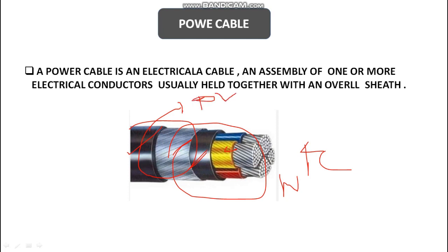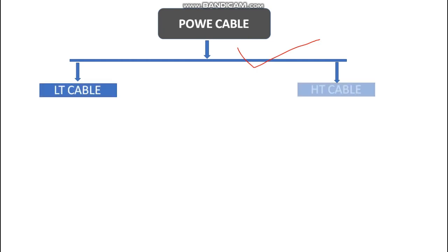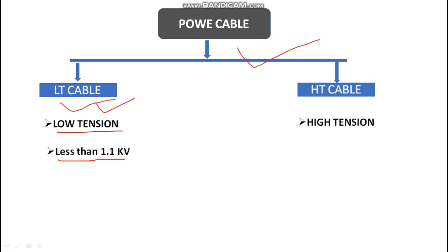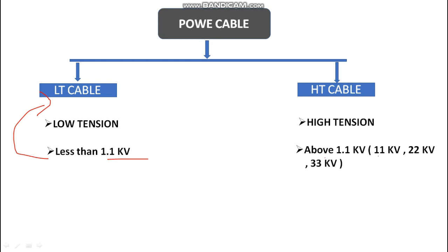Power cable also has types: LT cable and HT cable. LT cable means low tension cable, and HT cable means high tension cable. LT cable generally carries voltage less than 1.1 kV — we use 440 V in three-phase power transfer, and 220 V for single phase. More than 1.1 kV becomes HT cable, so 11 kV line, 22 kV line, and 33 kV line are all HT cables.